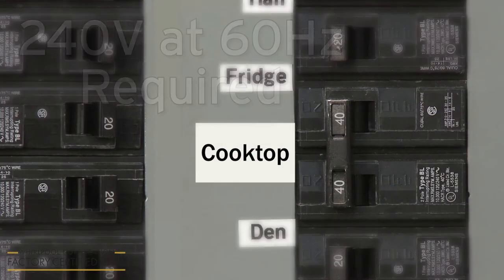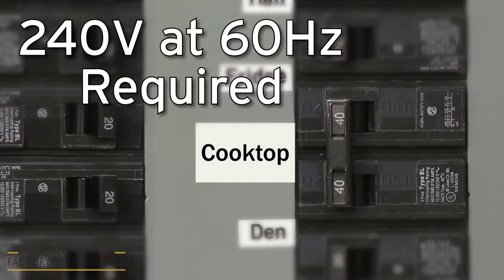The electrical supply for the appliance must be 240 volts at 60 hertz. A dedicated 40 amp circuit is required.